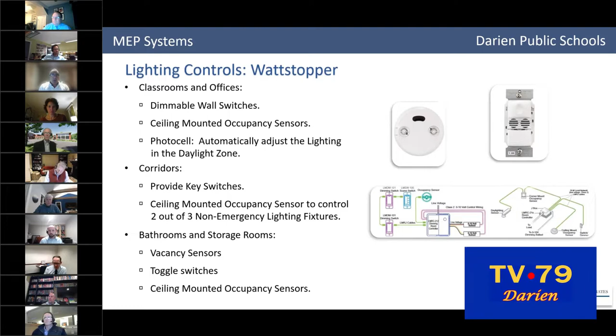In the corridors, wherever we're doing new fixtures, we're looking to have key switches installed instead of regular toggle switches, to avoid students turning off the lights in the corridor—only custodial staff or staff members with a key can turn them on. Ceiling mounted occupancy sensors will control 2 out of 3 non-emergency lighting fixtures, giving two levels of control: every third fixture works only with the key switch, and the other two work with occupancy sensors. That way the corridor never goes totally dark during the day—if everyone is in classrooms for a while, there will always be lighting in the corridor, meeting all requirements.